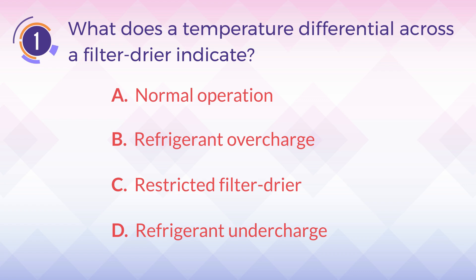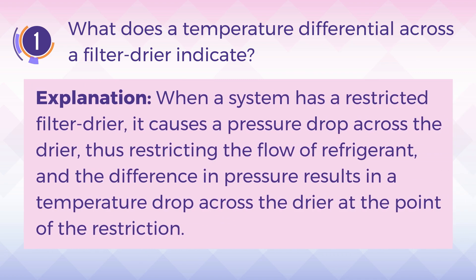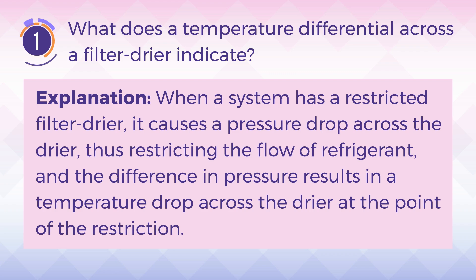The answer is C. Restricted filter dryer. Explanation: When a system has a restricted filter dryer, it causes a pressure drop across the dryer, thus restricting the flow of refrigerant, and the difference in pressure results in a temperature drop across the dryer at the point of the restriction.